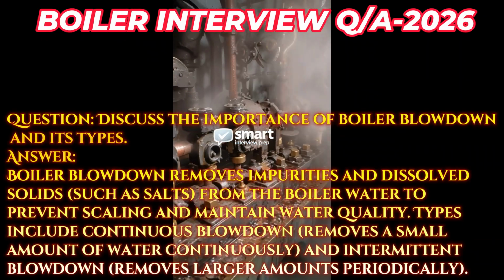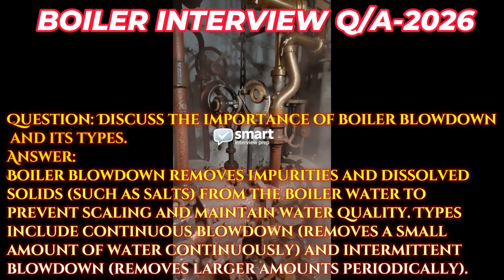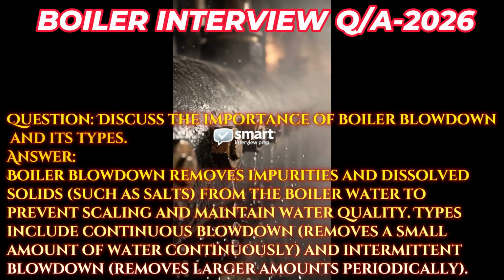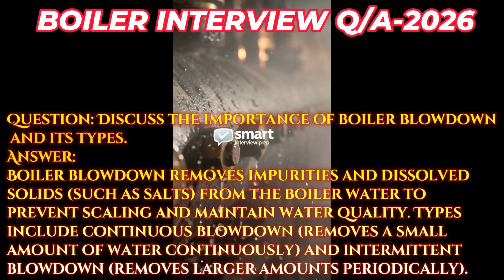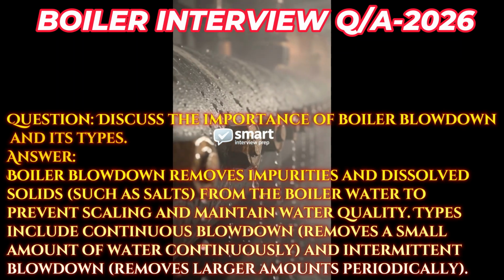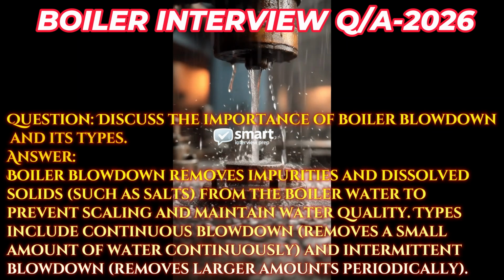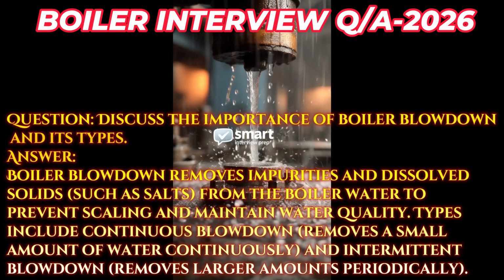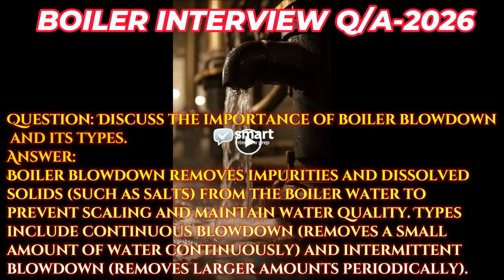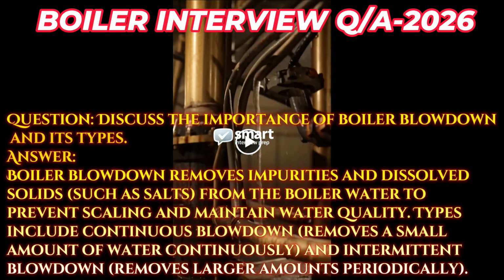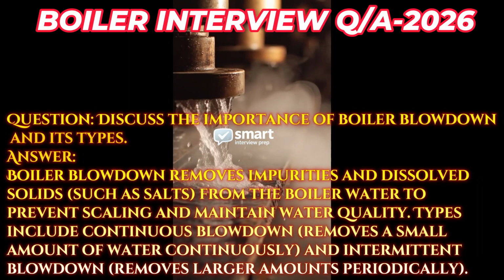Question: discuss the importance of boiler blowdown and its types. Answer: boiler blowdown removes impurities and dissolved solids, such as salts, from the boiler water to prevent scaling and maintain water quality. Types include continuous blowdown, removes a small amount of water continuously, and intermittent blowdown, removes larger amounts periodically.